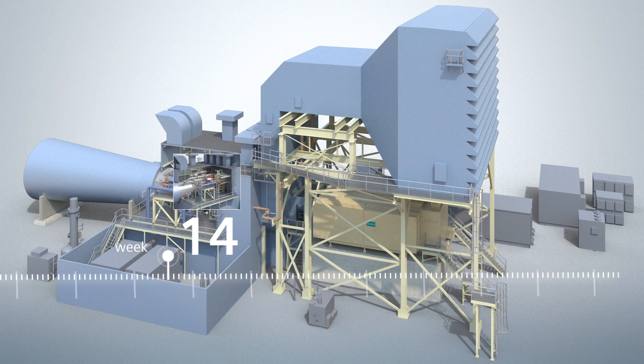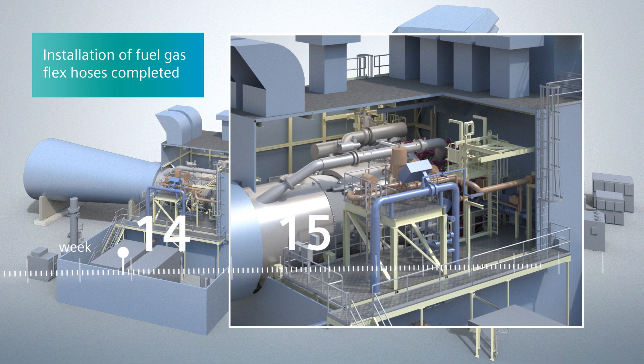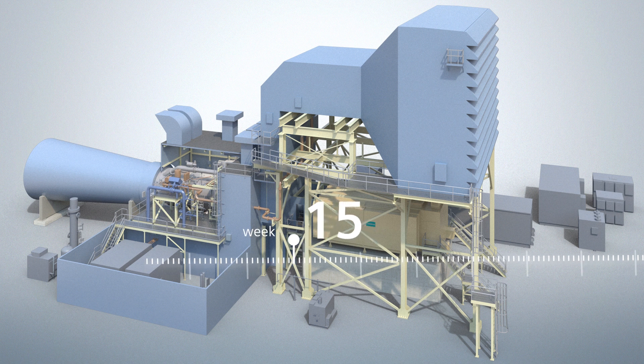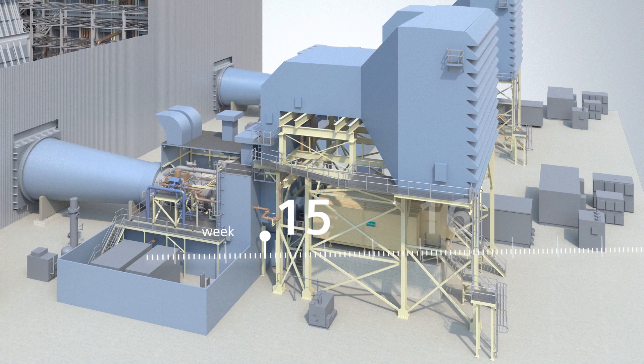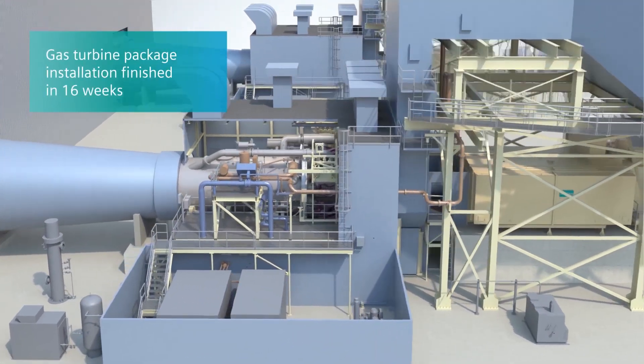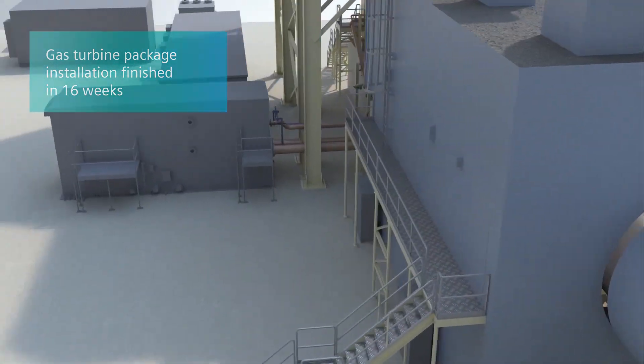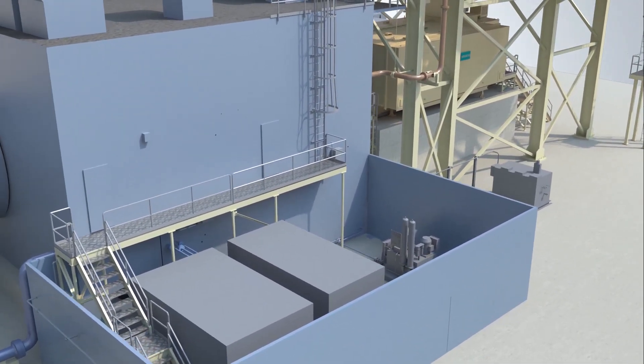In the final couple of weeks, the piping is completed for the gas turbine inlet heating and fuel gas systems. In week 15, the last step of the mechanical assembly — the final alignment of the gas turbine generator train — is performed. In just 16 weeks, the entire gas turbine package is constructed, and in only 5 months, the Siemens gas turbine unit is ready for operation.